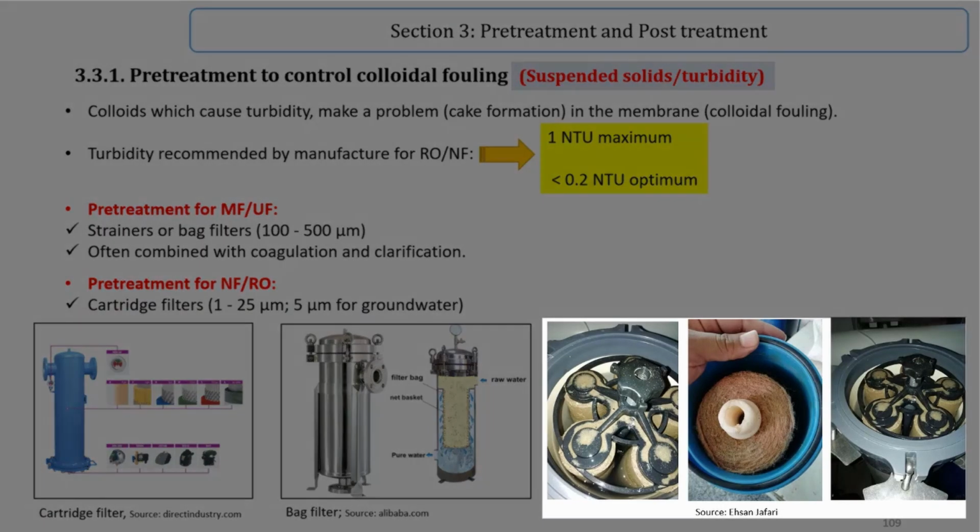I have taken these photos to show you the pretreatment filters after some months of operation. But it has to be noted that these filters have to be cleaned using washing or replaced to prevent damage to the membrane.